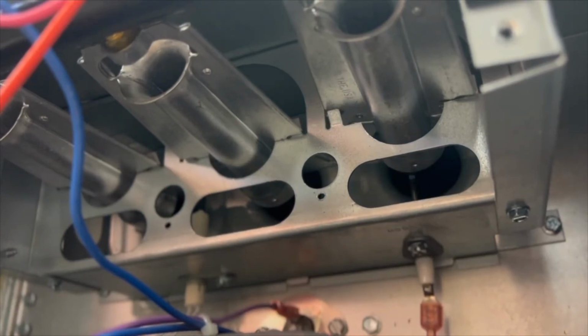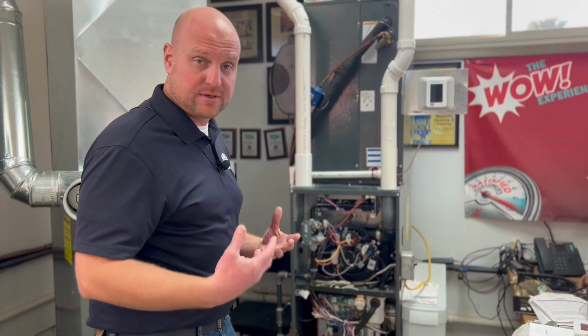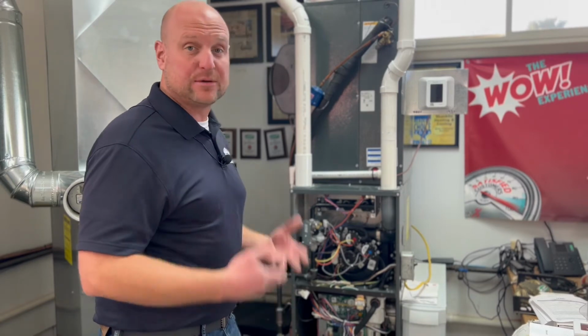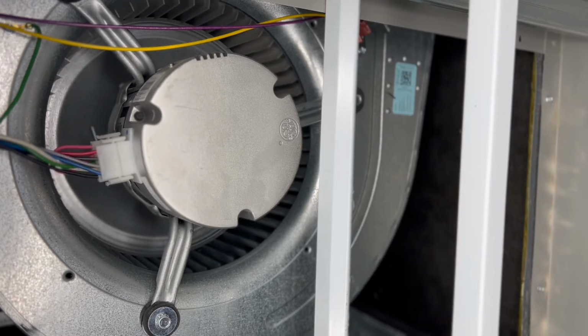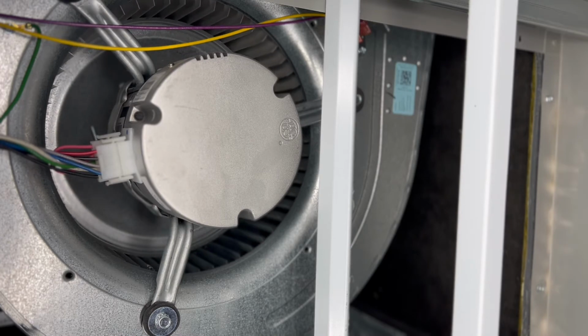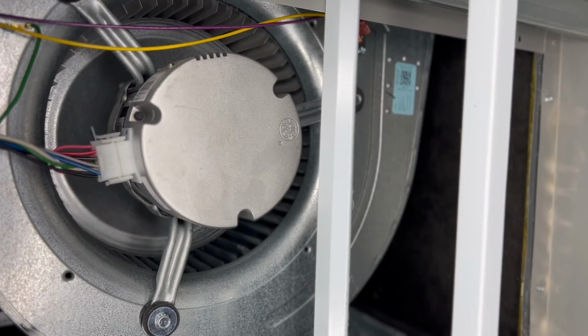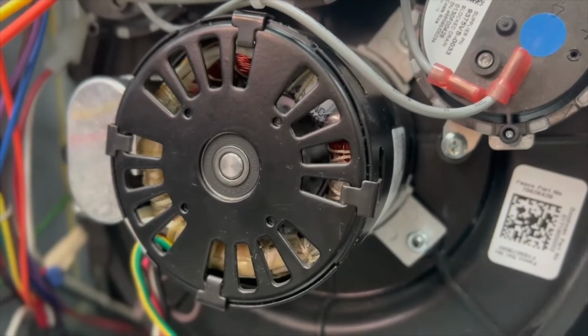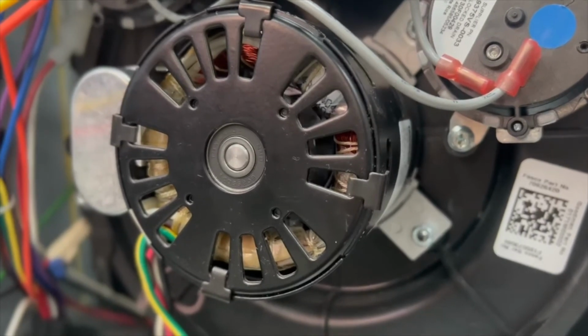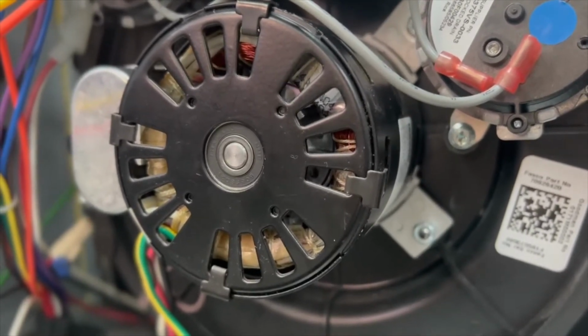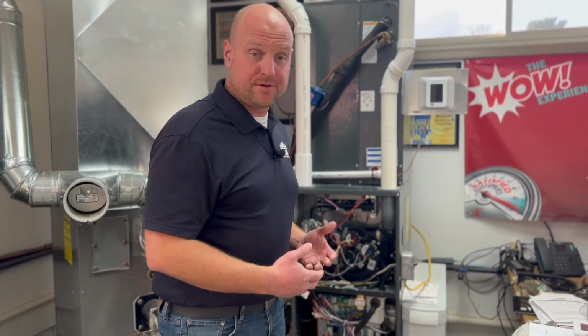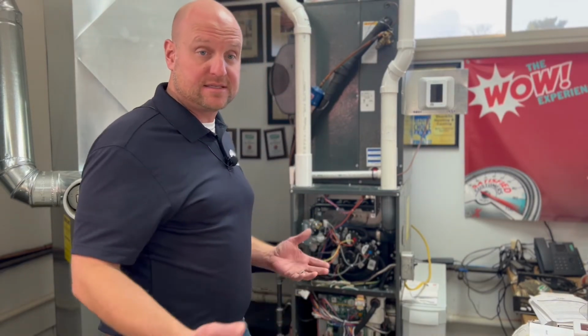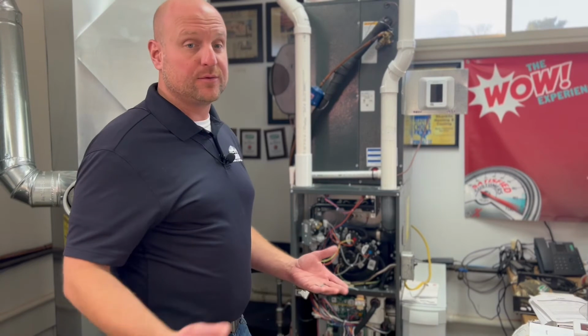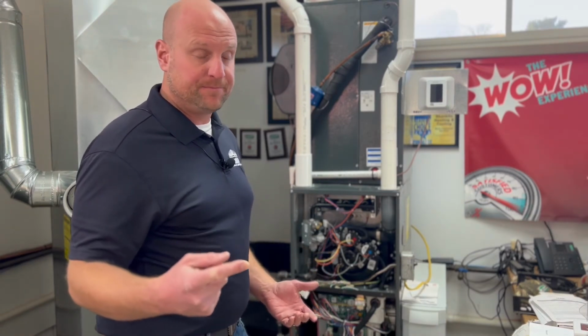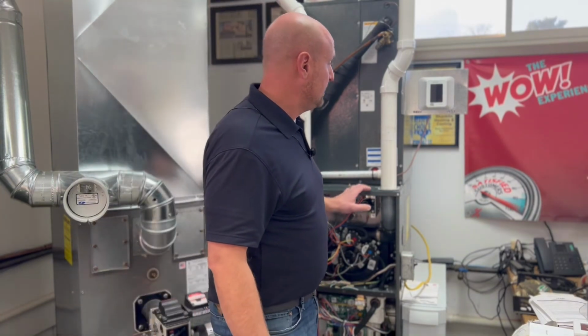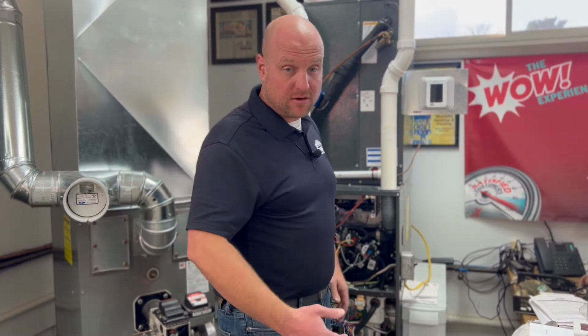At this point, the circuit board is going into another timer mode, because we need to get rid of the rest of the heat in this furnace. It's going to allow the blower motor and draft inducer to continue to run for roughly 90 seconds. That will remove any excess residual heat and any flue gases that are still inside of the heat exchanger. At this point, the furnace is going to be at rest, or in standby as we call it. It is done with its full cycle of operation, and it's just going to wait again for the thermostat to make the next call for heat.